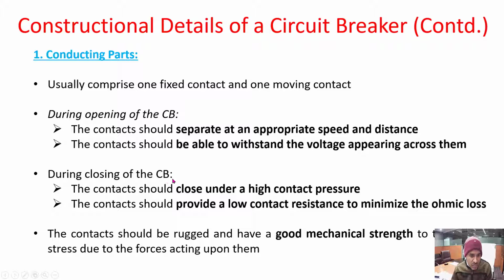And then during closing of the circuit breaker, what should happen? The contacts should close under a high contact pressure, because even a small contact resistance will cause huge heat loss, I square R loss, and that will cause heating up and ultimately damage the circuit breaker itself. Therefore, the contacts should provide a low contact resistance to minimize the ohmic loss. That is very, very important. High contact pressure and low ohmic loss, that is what is required for closing the circuit breaker.